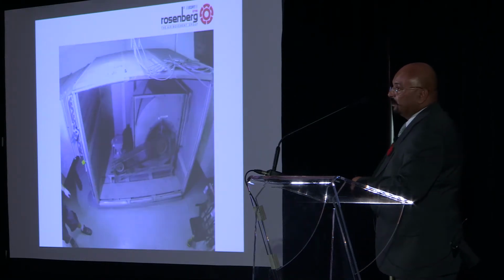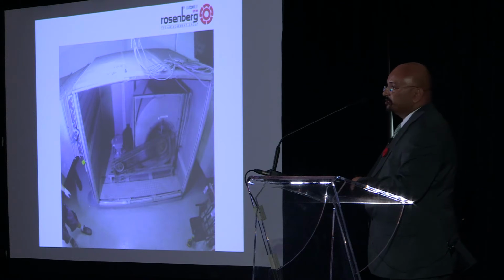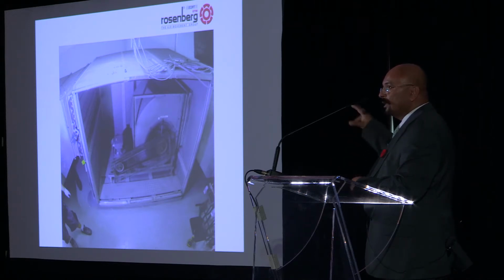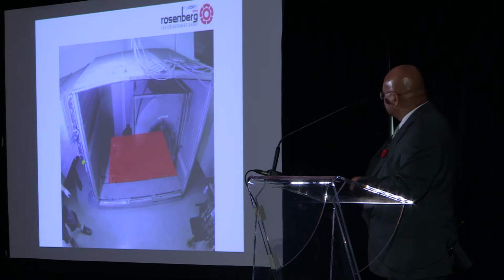So this is an example of how it looks at the installation site for a single belt-driven fan. Look how dirty the floor is, and the other areas as well. So it's very difficult for a person to go in to clean the inside area. This is the actual area which looks very dirty, because of the different lubricants, the belt, all that create a lot of dirt inside.